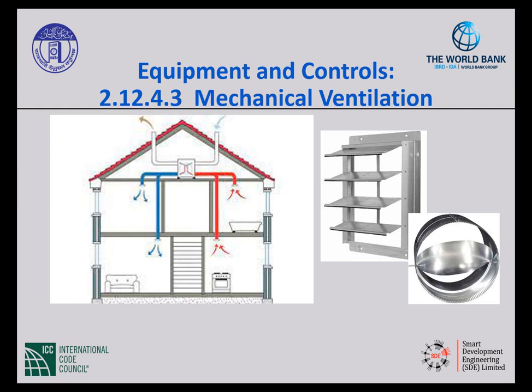Then you have automatic or gravity dampers that close when the system is not operating, which have to be provided on your intakes and exhausts. So I'm going to make sure that I have my ventilation system, but there has to be an auto shutoff. So if, again, there's a fire outside, I don't need all that smoke in my building, I'm going to shut off my ventilation system for a little while. And then anywhere where I have an intake or an exhaust, I'm going to have a damper, whether it's automatic or gravity, depending on what the mechanical code would require me to have. Those dampers have to close when I'm not exhausting or being required to bring in air.